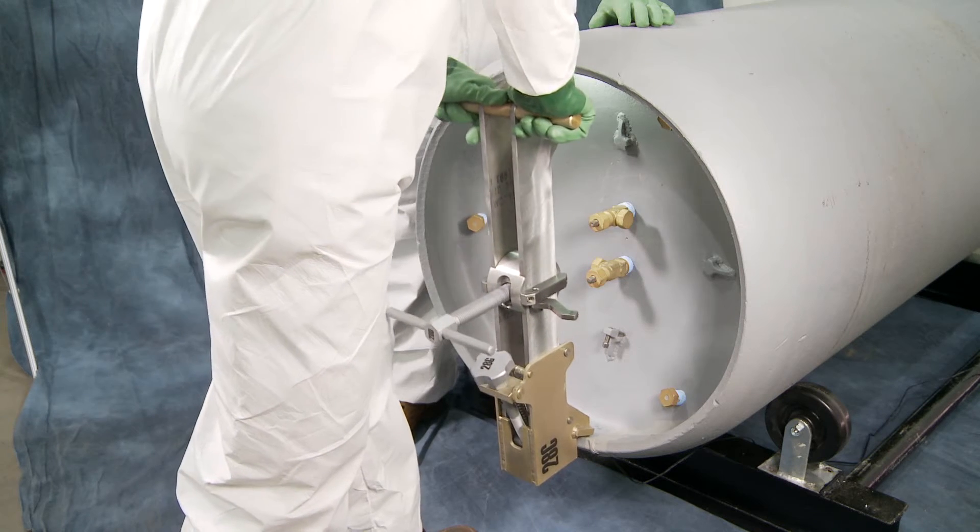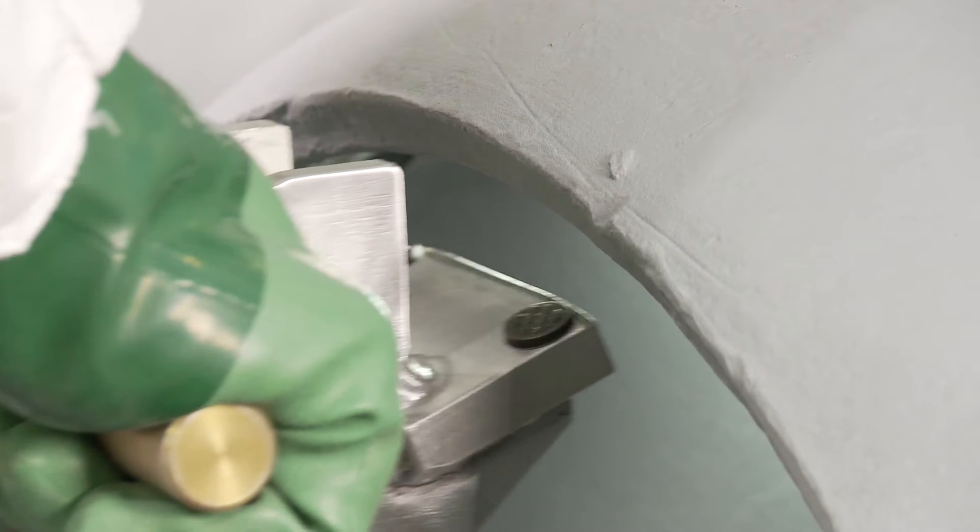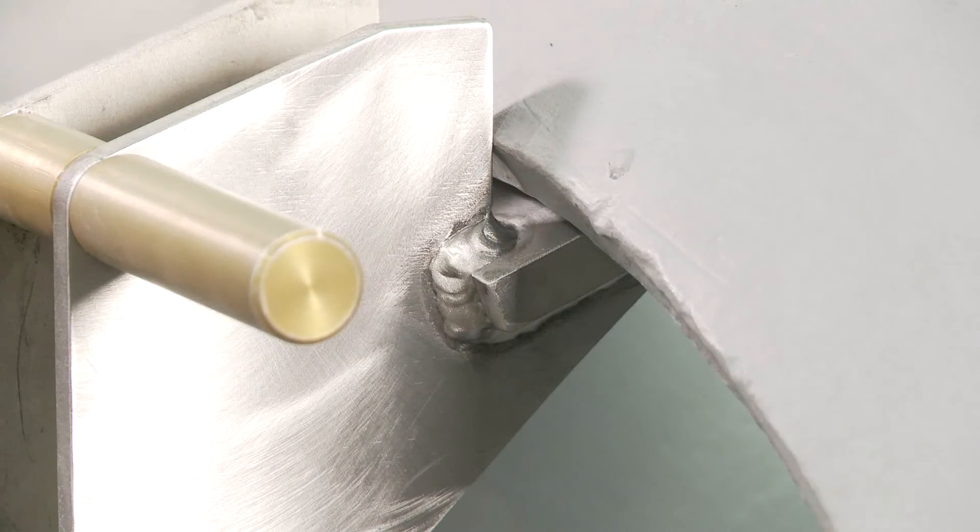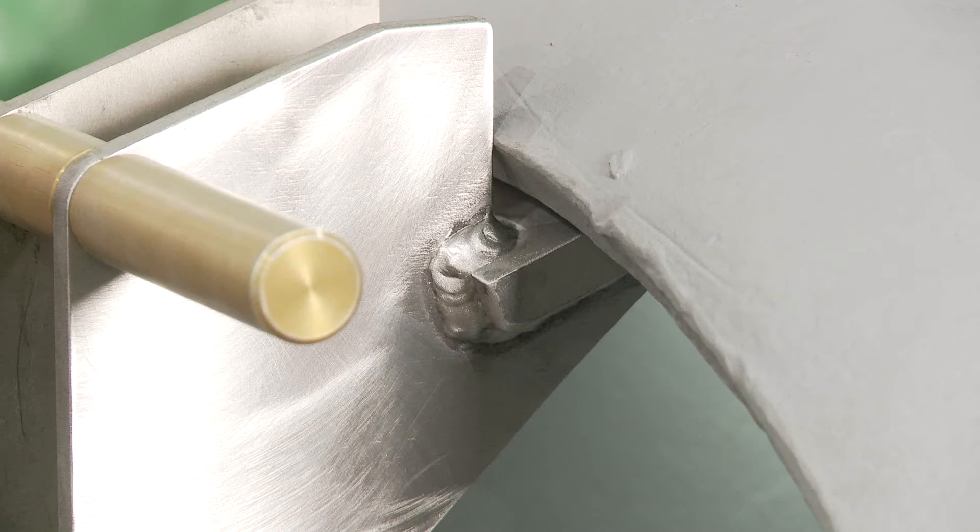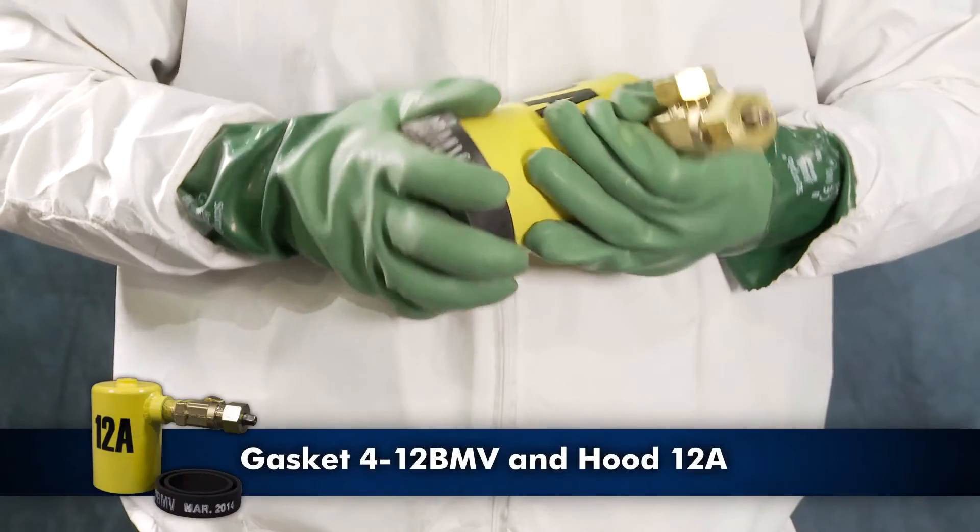Compress assembly downward using handles. Insert the upper end of bar assembly inside the chime. Reduce resistance to allow unit to expand into the upper chime lip with the upper bar extensions resting on the outside of the chime. Place a new gasket on hood 12A.